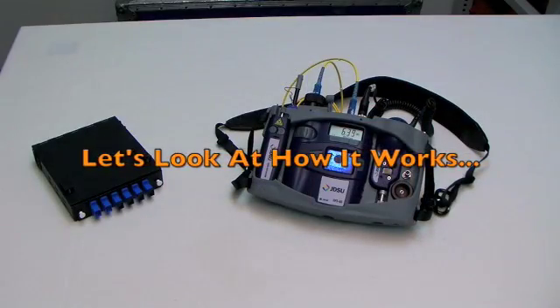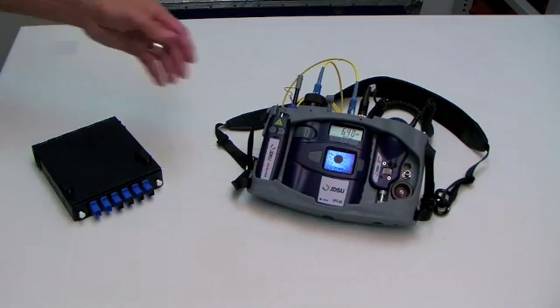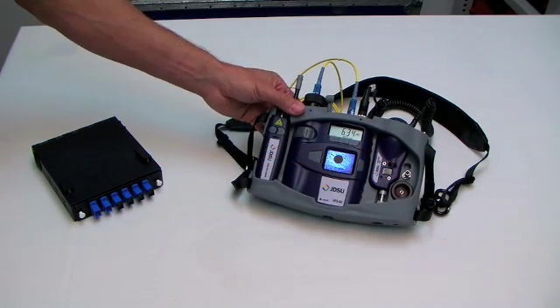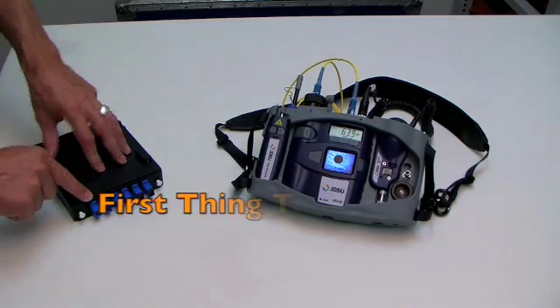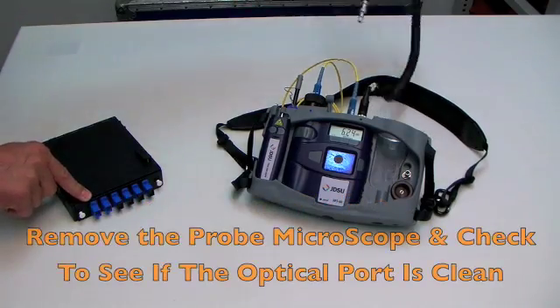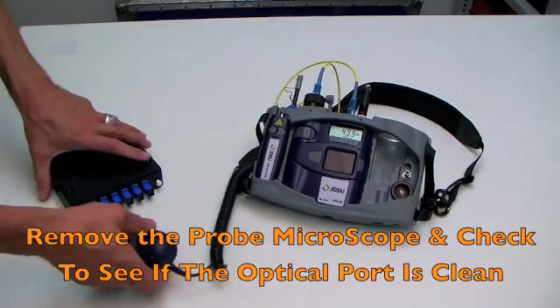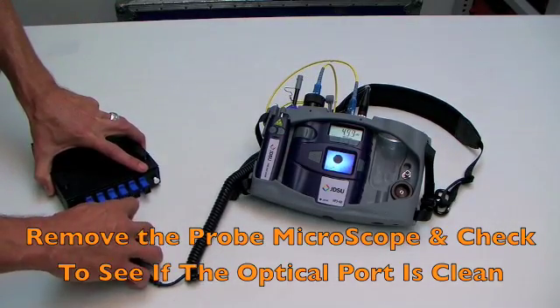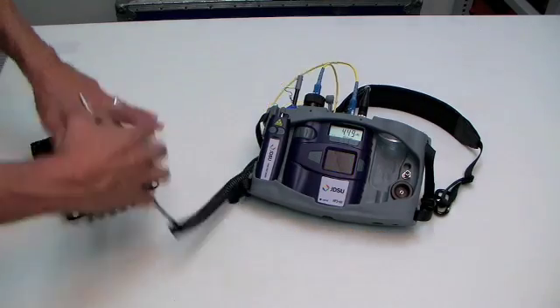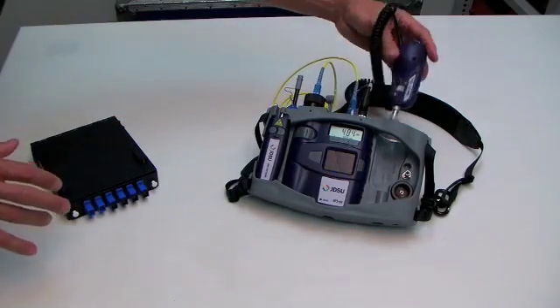Now let's look at how this essential fiber cleaning kit works. If a technician is using this kit to go out in the fiber plant and check light levels or loss on an optical channel, the first thing they're going to do is remove the probe microscope, plug it into the optical port, and check to see if that port is clean. This port isn't clean, so the technician's going to want to clean it before he plugs his test lead into it.